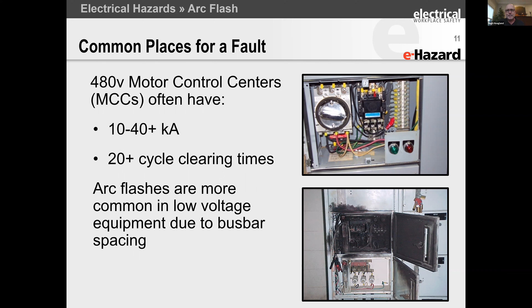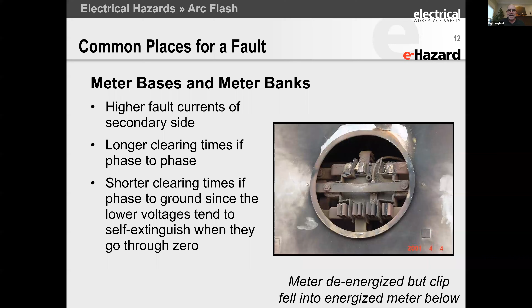Meter bases in the US have a substantial issue. Even though you can de-energize these stabs here, the bus is still energized, and it's not insulated, typically, in the US. So if your bus is like this, or any type of setting, even if it's not a meter setting, if you have parts that are energized while you're working and parts that are de-energized, if anything can break... What happened was a stab broke off of this meter base, or the meter itself, and fell into the bus work that was energized, even though the stabs were de-energized, and it blew up and burned this person's face. And we'll show you what happened to him a little bit later.